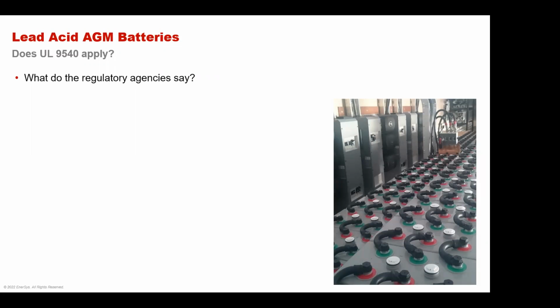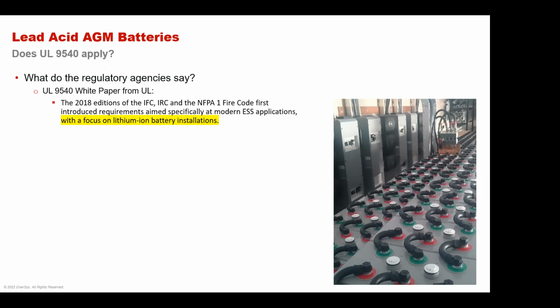So lead acid AGM batteries, does UL 9540 apply? Well, technically yes, but let's take a closer look here and see what's going on. I found this UL 9540 white paper from UL online, and one of the sentences says the 2018 editions, which is the second edition of the IFC, IRC, and NFPA Fire Code, first introduced requirements aimed specifically at modern energy storage system applications with a focus on lithium-ion battery installations.